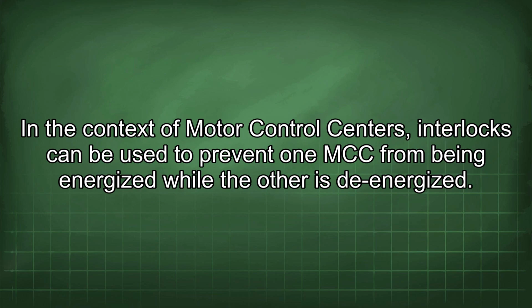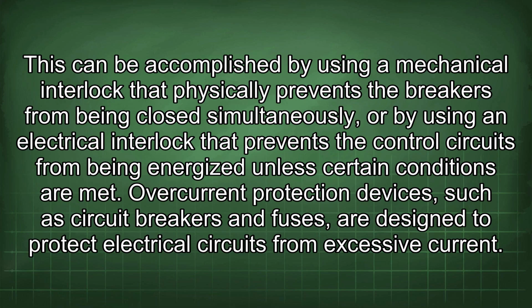In the context of motor control centers, interlocks can be used to prevent one MCC from being energized while the other is de-energized. This can be accomplished by using a mechanical interlock that physically prevents the breakers from being closed simultaneously, or by using an electrical interlock that prevents the control circuits from being energized unless certain conditions are met.